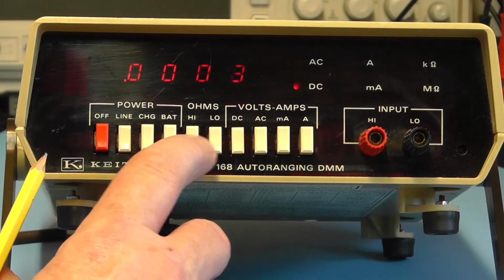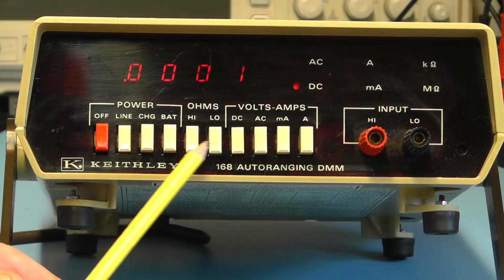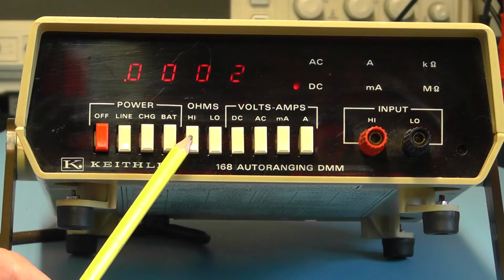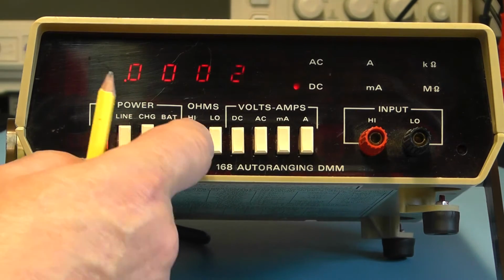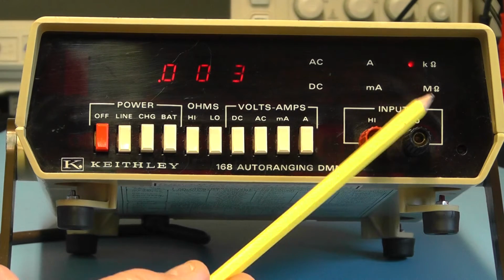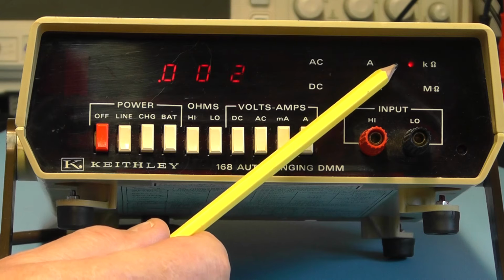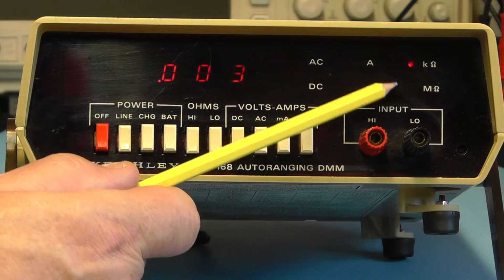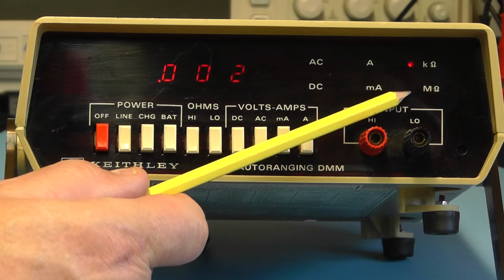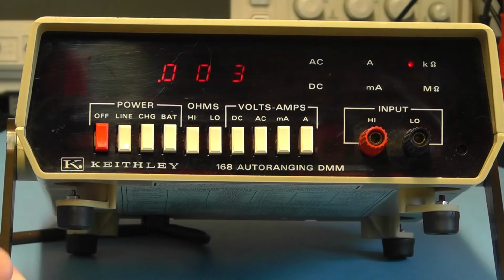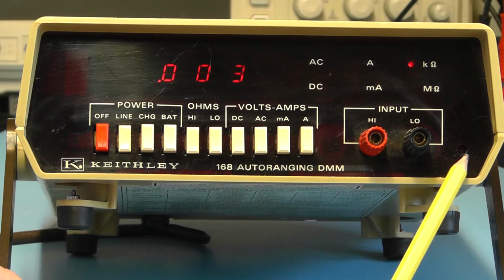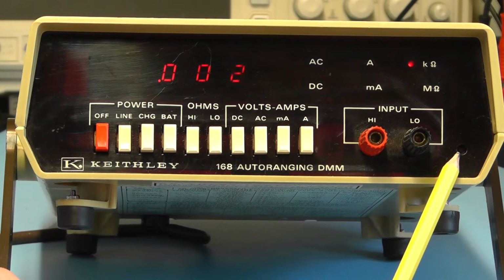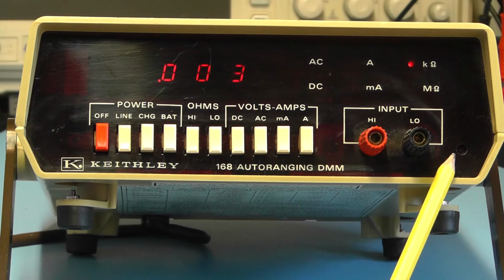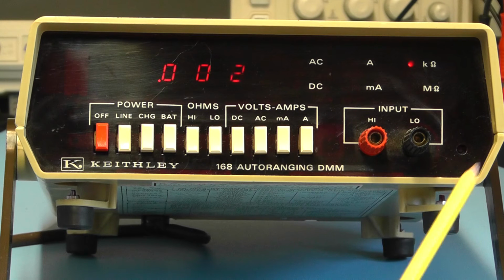Release the current key. We have 2 keys here associated with the ohms readings, a high and low ohms, so you have 2 ranges basically. When you press in the ohms button, you find that one of the LEDs lights up here. At the moment it's on kilo ohms, so you'll see the kilo ohms LED is lit. If the meter then measures a resistor in mega ohms, it'll switch over to the mega ohms LED just below. In the far right hand corner you have a little opening in the front panel, and behind there you have a preset resistor which can be used to zero the meter. For example, on the ohms range, you could short your leads together and then zero the meter using the little trimmer behind that slot on the front panel.